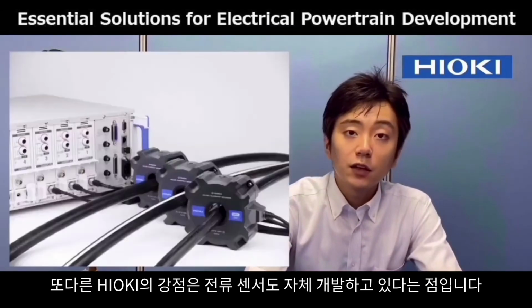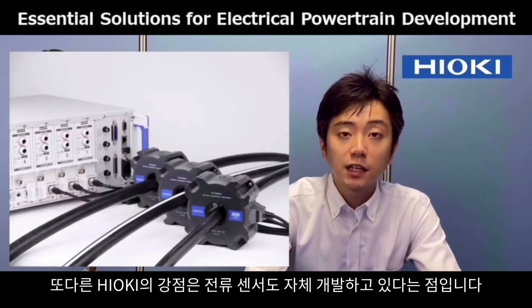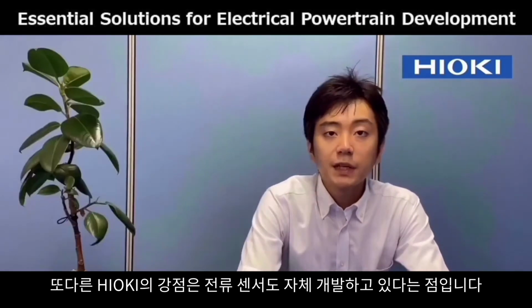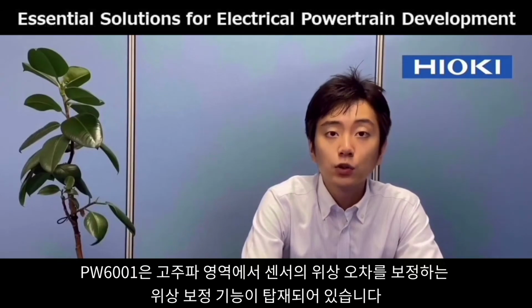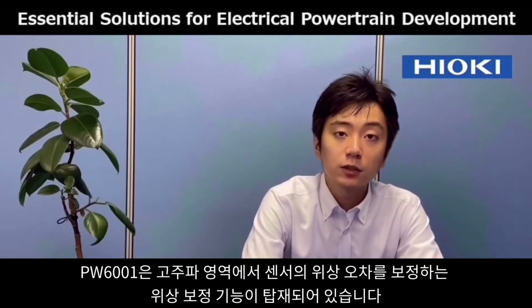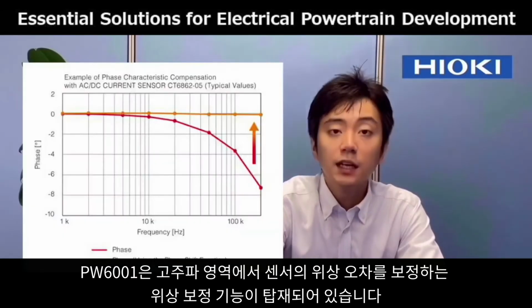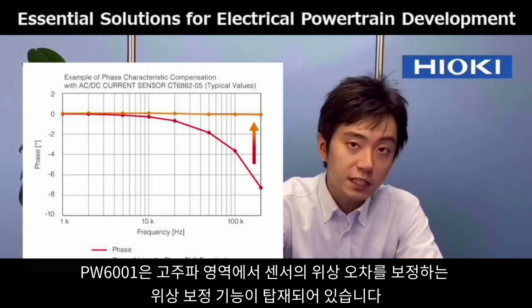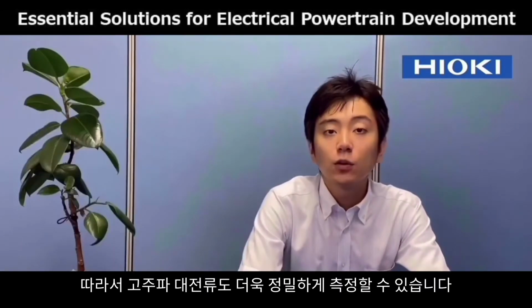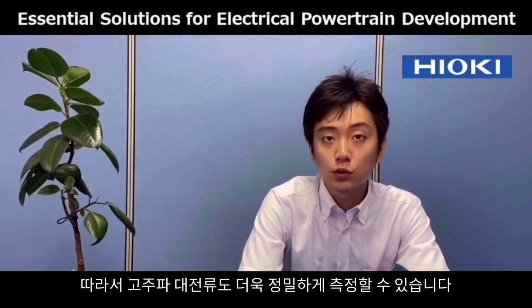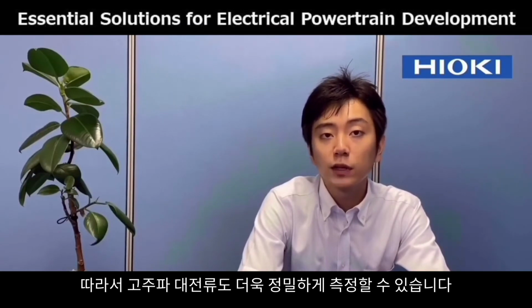Another strength of Hioki is that we develop all current sensors and power analyzers ourselves. The PW6001 is equipped with a phase shift function that corrects or shifts the phase error common to all current sensors. This makes it possible to measure large current or power across wide bandwidths even more accurately.